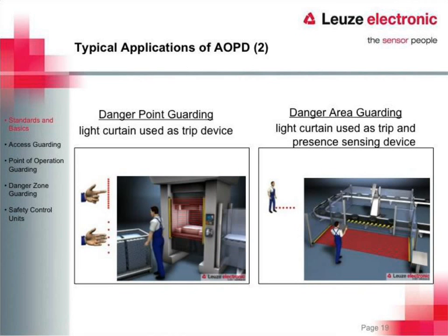The areas where we would typically see a light curtain are danger point guarding or danger area guarding. For danger point guarding, this is going to be up close and personal with the machine — manually fed, with the light curtain very close to the danger point. We're going to have a smaller resolution than we would see on a multi-beam, which means a hand can't be inserted as far before tripping, letting us get a lot closer to the machine. This is where you see it on process machines where they're hand loading and unloading, and also on press brakes and trim presses.